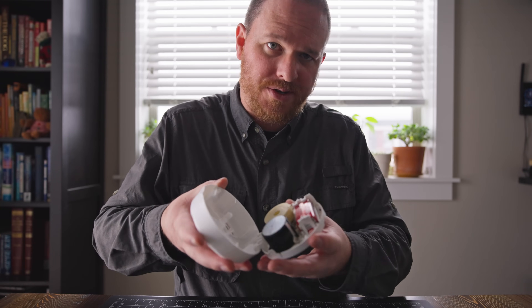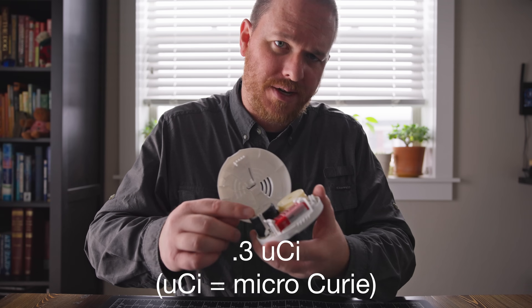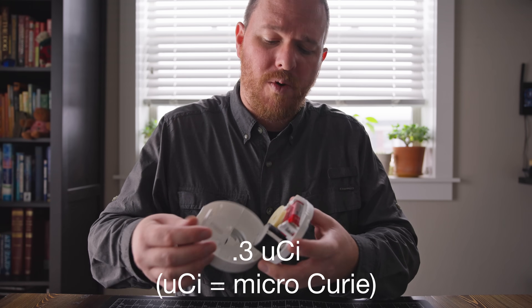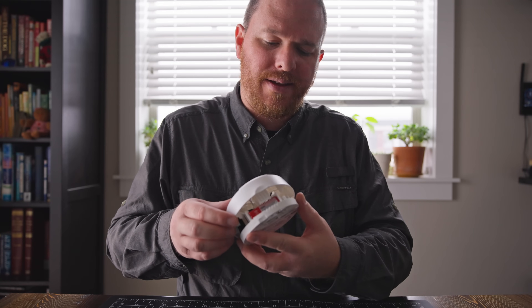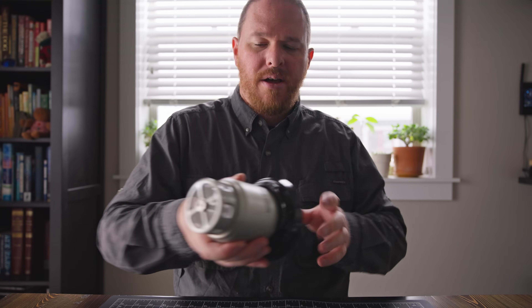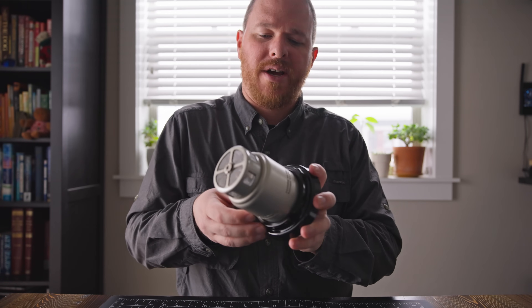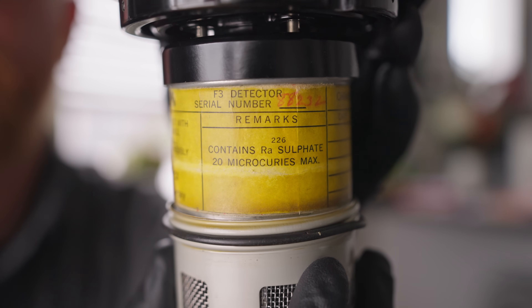In these types of smoke detectors, there's usually around 0.3 microcuries of americium-241. That's fairly small, and they will be very active if you get close to them, but that alpha radiation only travels about a couple inches in air. The Pyrotronics F3 smoke detector uses radium-226 and uses 20 microcuries of radioactive material.